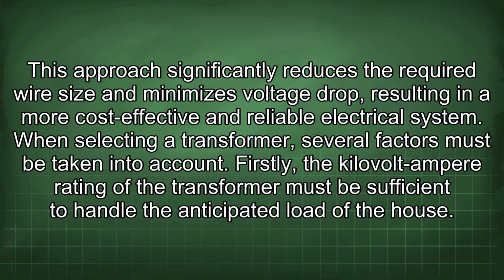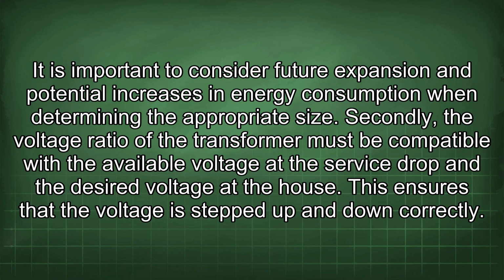Firstly, the kilovolt-ampere rating of the transformer must be sufficient to handle the anticipated load of the house. It is important to consider future expansion and potential increases in energy consumption when determining the appropriate size. Secondly, the voltage ratio of the transformer must be compatible with the available voltage at the service drop and the desired voltage at the house. This ensures that the voltage is stepped up and down correctly.